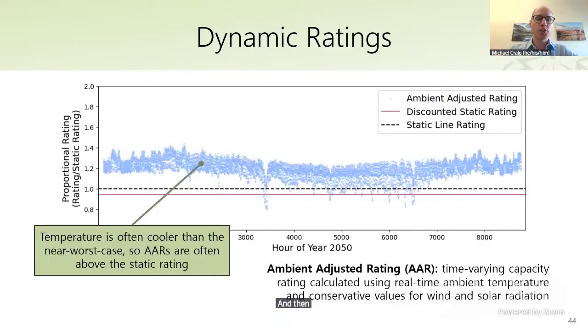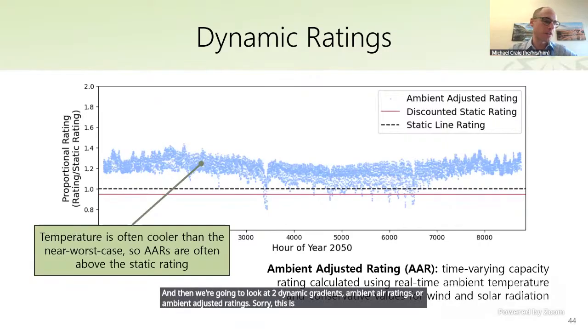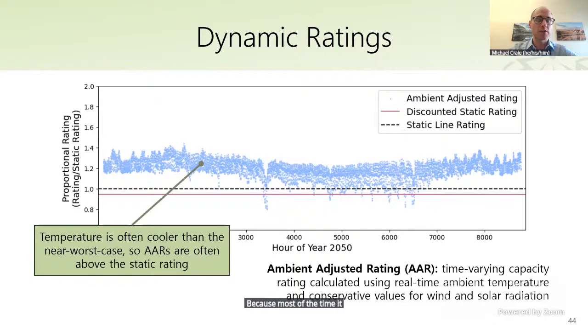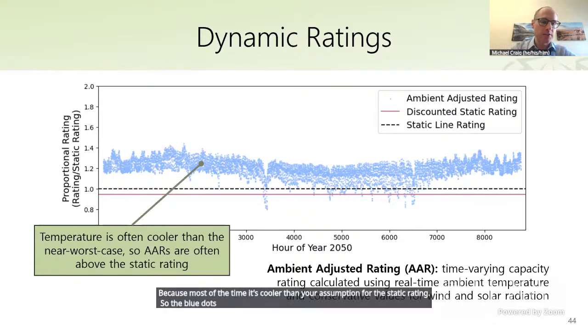Then we look at two dynamic ratings: ambient air or ambient-adjusted ratings, which are used in Texas and other parts of the country. These give you more rating, reflecting more capacity on the line, because most of the time it's cooler than your assumption for the static rating. The blue dots here are your hourly ratings—you can see them above these solid lines.